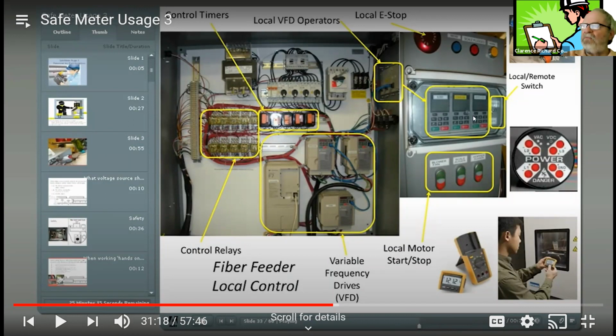On the outside, I have some instrumentation on these VFDs where I can actually read what's happening on my VFDs from outside, instead of having to do it on the inside and do the programming. So you can pop these things right off the VFDs and put them on the outside. Start-stop buttons are there as well. These circuit breakers have safety guards over them where you really can't get your fingers in there, and that's always a good design.